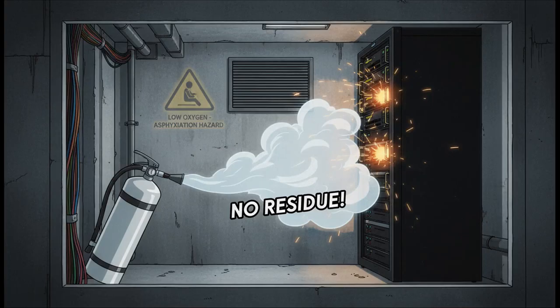All right, let's talk about carbon dioxide, or CO2 extinguishers. These are fantastic for Class B and C fires, mainly because they are clean. They leave zero residue behind. But there are some major trade-offs. They're pretty useless on Class A fires, and here's the big safety warning.